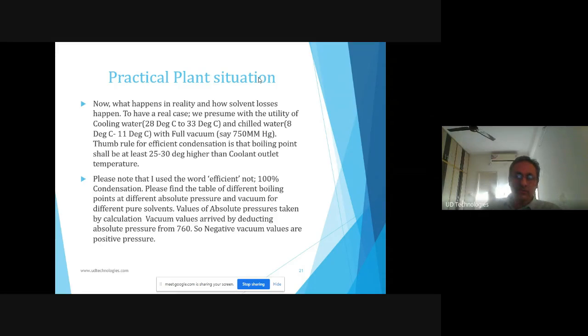Thumb rule. What is the thumb rule? For efficient condensation, the condensing temperature should be at least 25 to 35 degrees higher than the coolant outlet temperature. For example, if we have to condense water at atmospheric pressure, it is 100 degrees centigrade, so cooling water is okay. But if you go for acetone, it is only 58 degrees. It can condense up to 30, and the outlet temperature will be around 33. The temperature difference is 30 plus 30, it is 63, so it will be somewhat higher. Because of that, we'll have to use the chilled water to cut down the vapor pressure arising at the outlet temperature of the cooling tower.